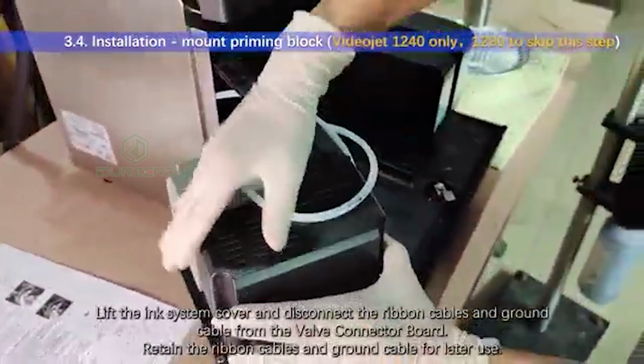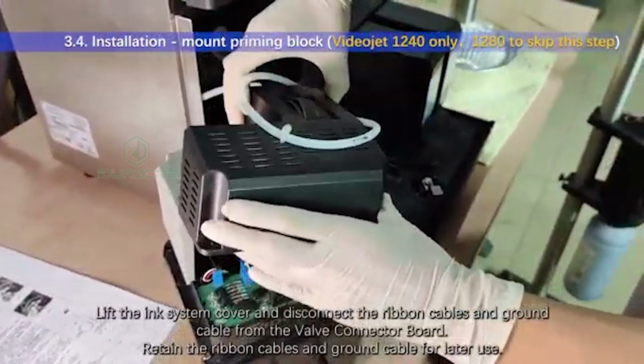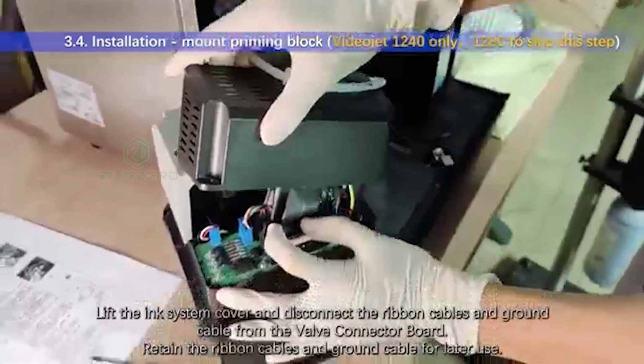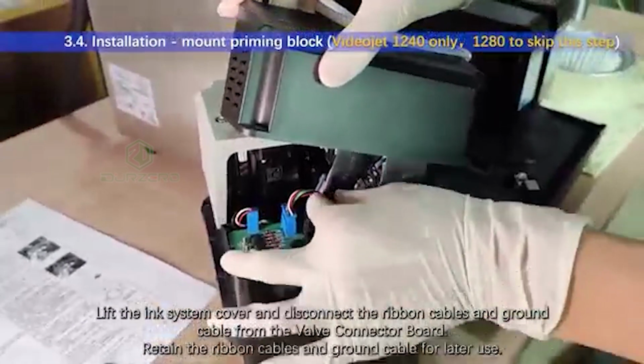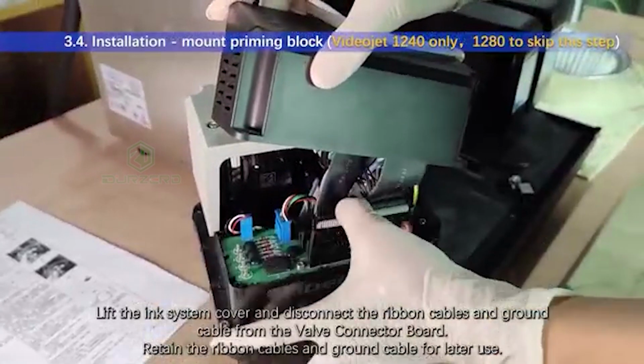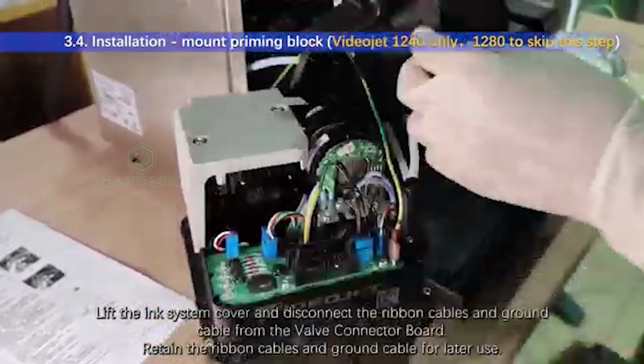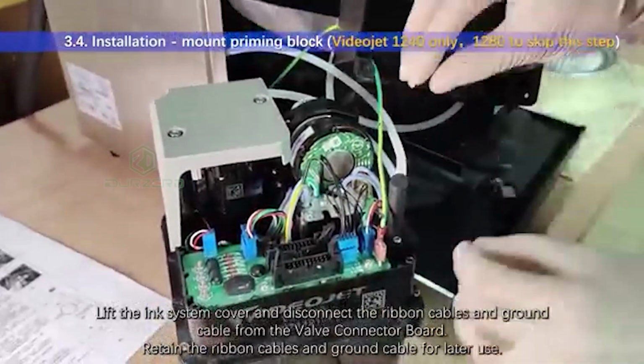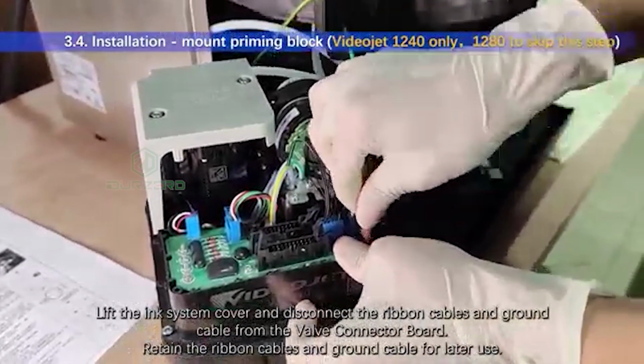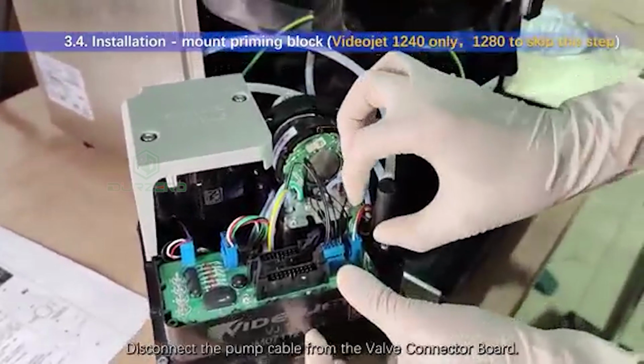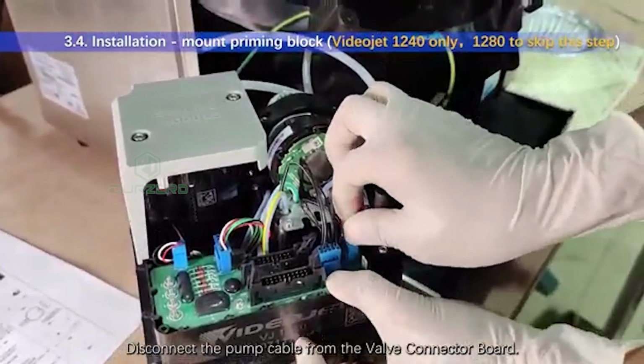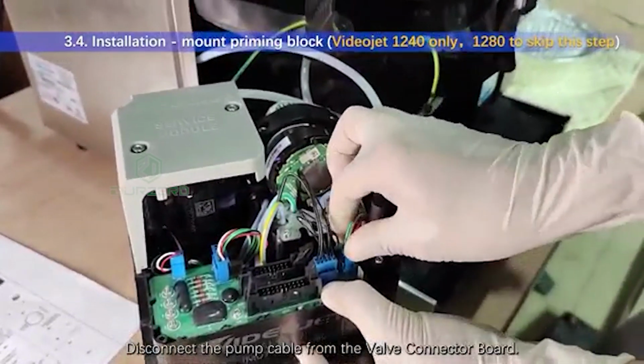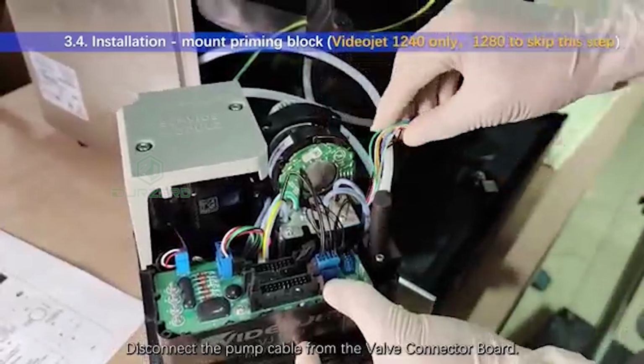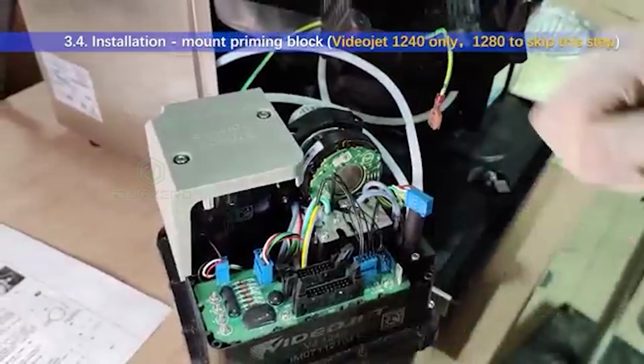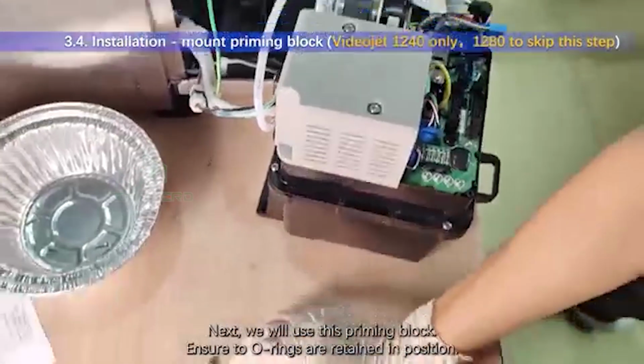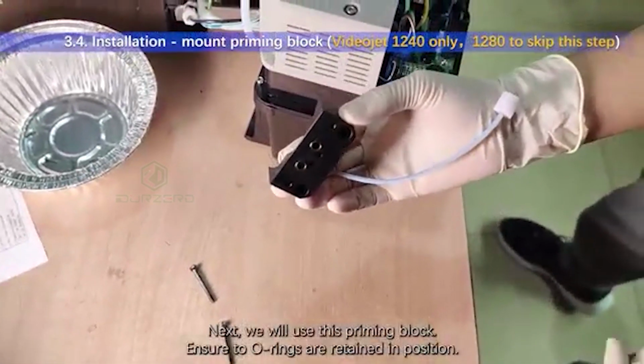Lift the ink system cover and disconnect the ribbon cables and ground cable from the valve connector board. Retain the ribbon cables and ground cable for later use. Disconnect the pump cable from the valve connector board. Next, we will use this priming block. Ensure two O-rings are retained in position.